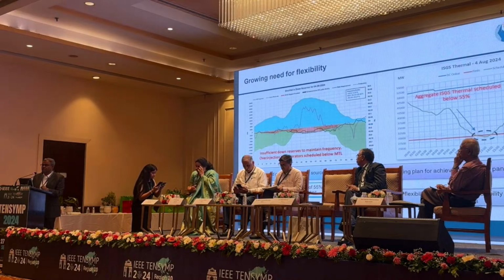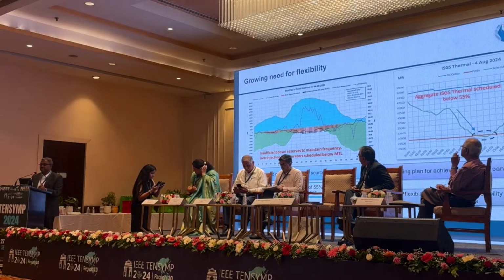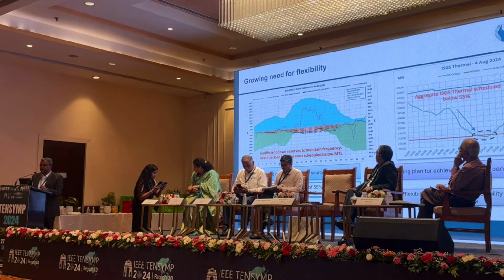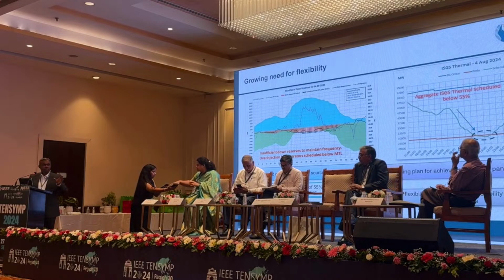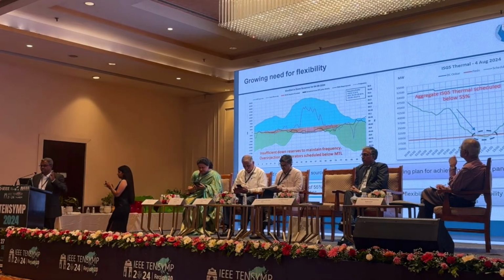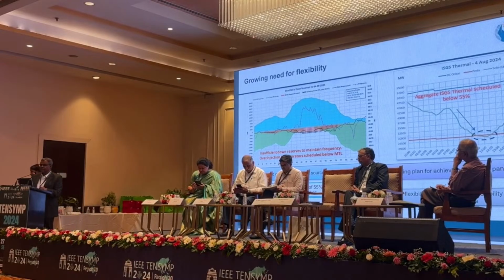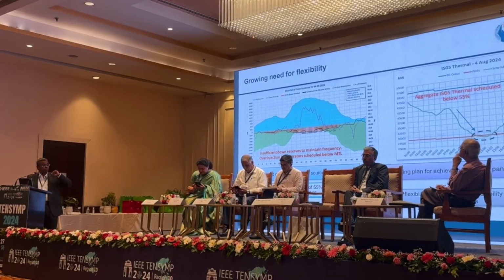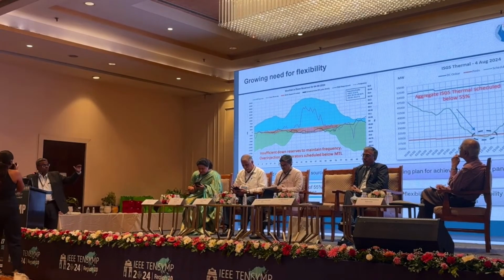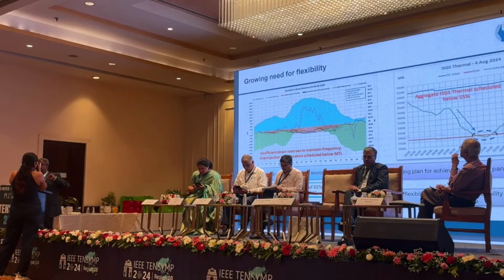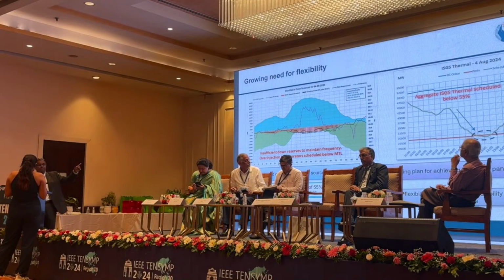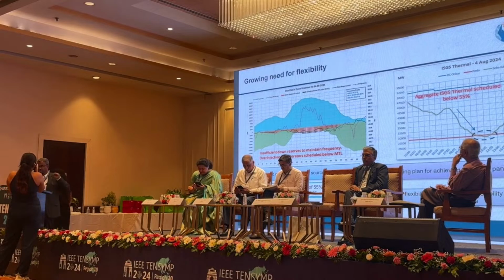Coming to the flexibility challenges, this is a recent plot from 4th of August. On the left hand side, we have high frequency during high solar hours. The dotted line shows the frequency. High frequency operation is happening and we are trying to reduce generation. The red bars at the bottom show us reducing thermal generation to absorb more RE, and we do not have down reserves available to reduce any further to absorb more RE.